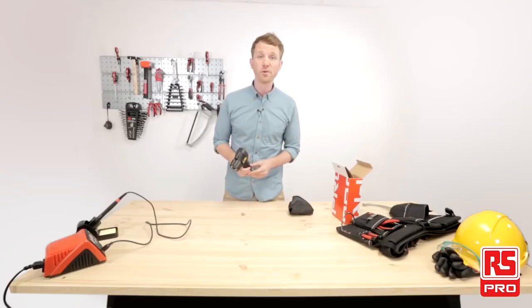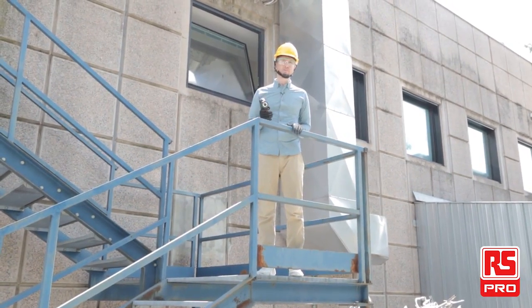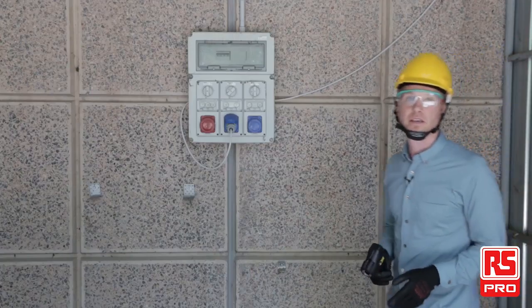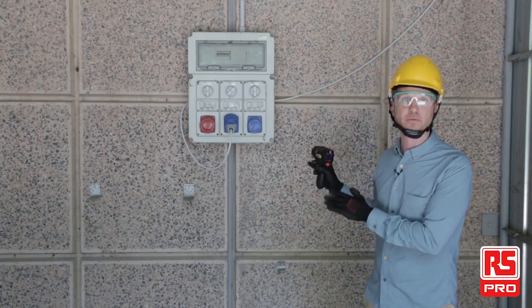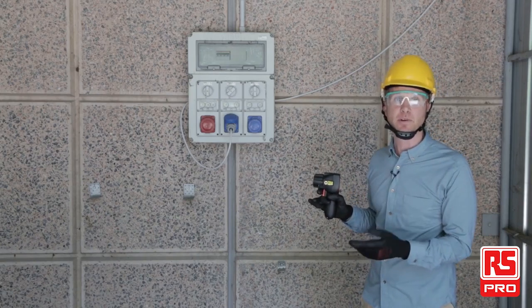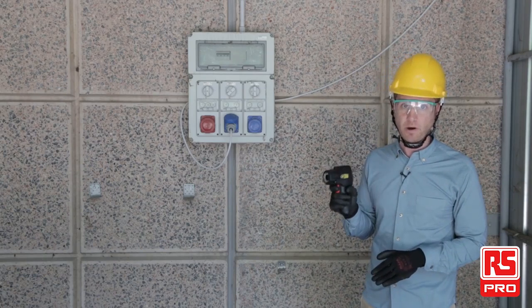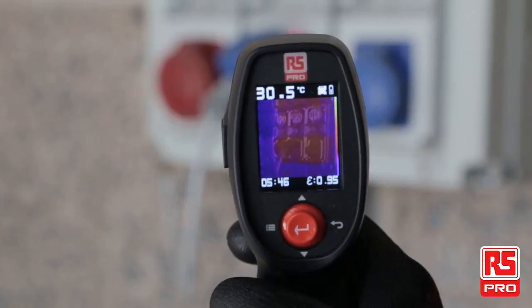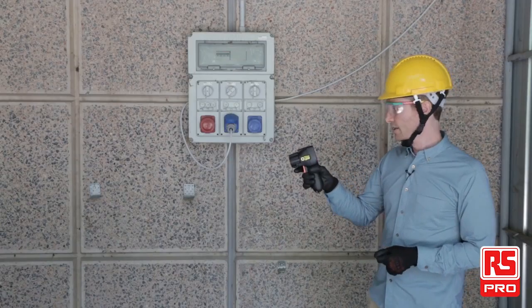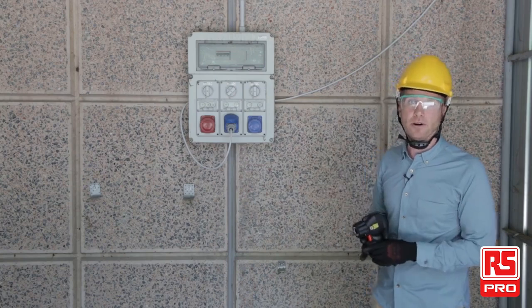And now let's see the TG-301 in action. Here we are outside. This is a typical example of everyday maintenance related to temperature control. Here we are outside and this is a pretty typical control panel. If we were going to perform maintenance on this, we would want to check the temperature, make sure there are no hot or cold spots. Thanks to the TG-301, we can do that from a safe distance before we begin our work. Looks like 30.3 degrees — perfectly safe temperature. Now we can begin our work.